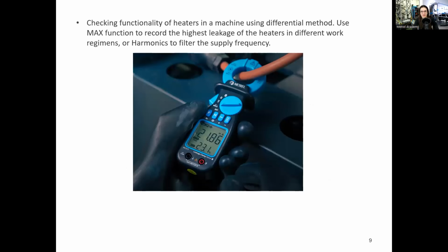In our next application, we can check the functionality of heaters in a machine using the differential method. In this case, we have the supply wires of the machine very easily accessible, which makes the differential method ideal for use. Again, we can use the max function to record the highest leakage of the heaters in the machine, or we can use the harmonics function to filter to only the supply frequency.